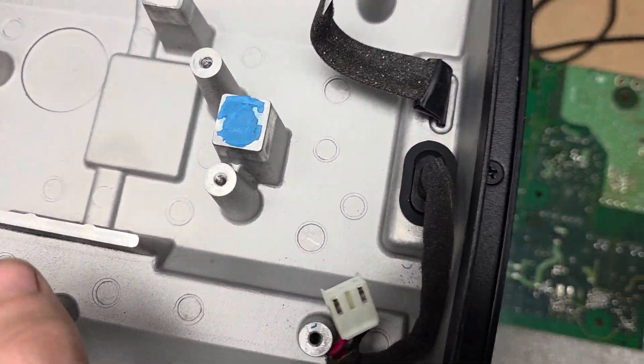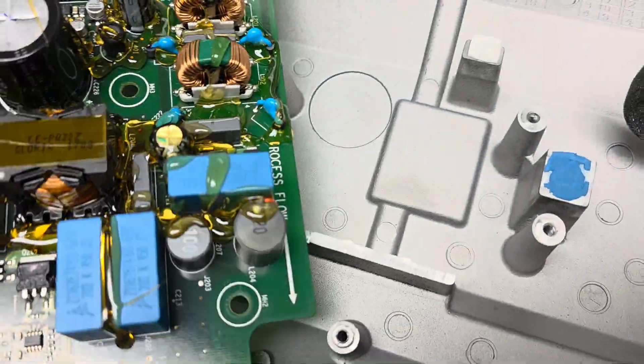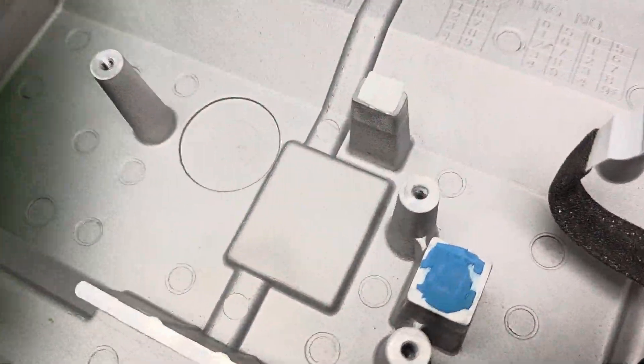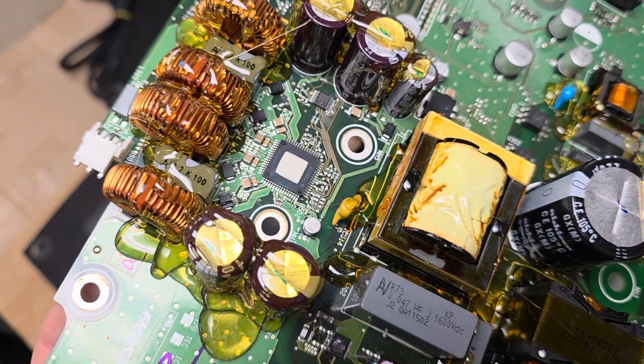When you replace the PCB, you want to put on new thermal pads. There are blue thermal pads here, and then there's a big thermal pad for this larger microcontroller right there.